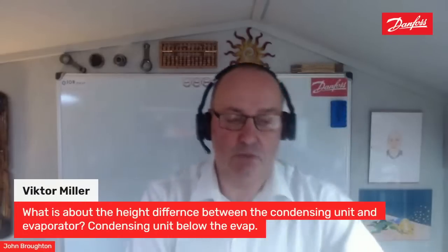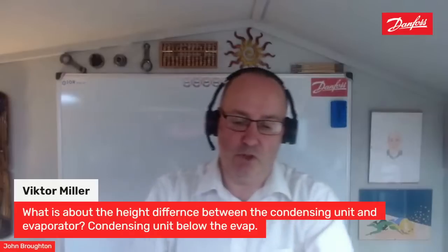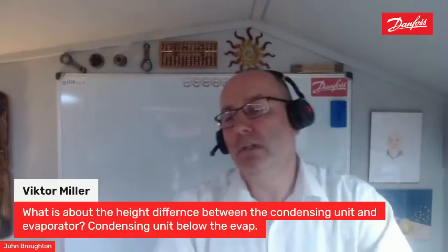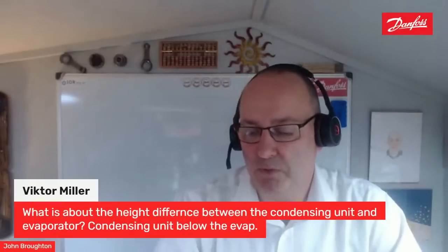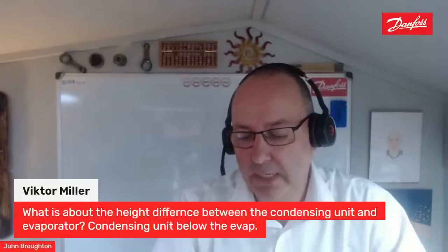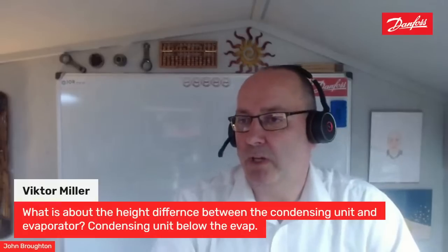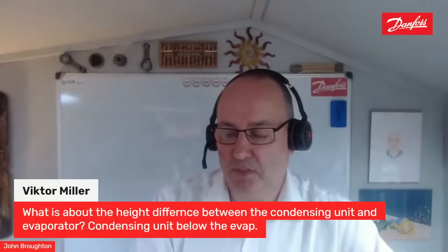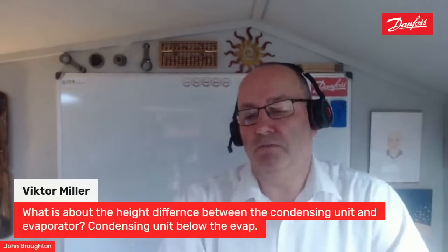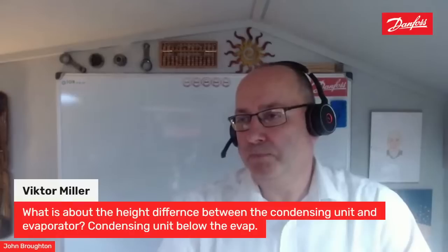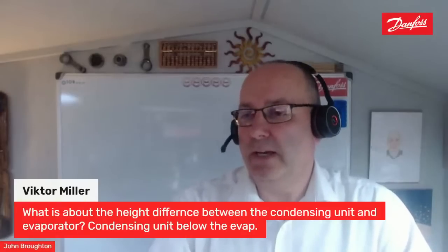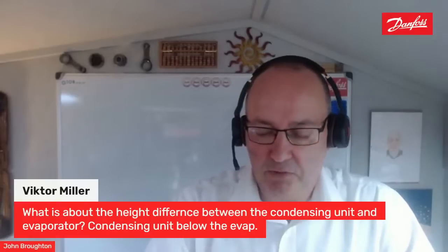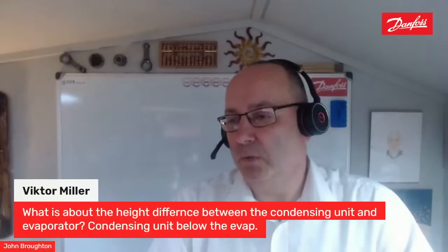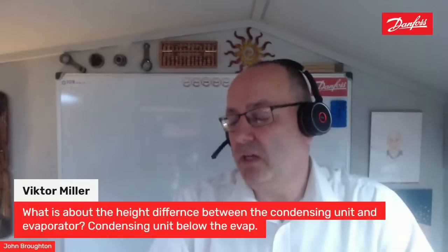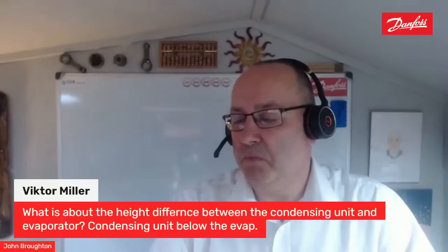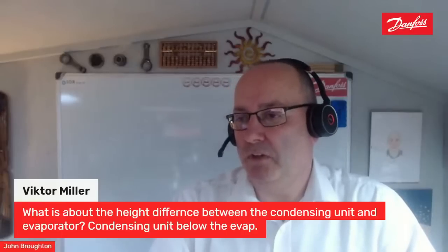And there's various rules of thumb as to whether it is every 2 meters, every 4 meters. If you're going through a building, generally people hide them within the fabric of the building, so they're about every 4 meters. Keep your velocity right and think about it logically. We've got to get oil back to that machine. So that is the most important, and we've got to keep that velocity right.